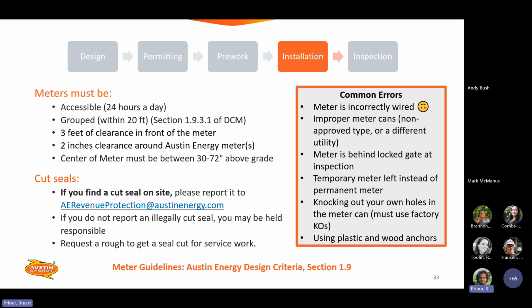Quick tip is also that it's going to be a 200 amp meter can with the bypass handle. This is for residential self-contained meters, but if it's not the right one... Also, if the meter is behind a locked gate at the time of inspection, we do need access to all that equipment. If you've left a temporary meter instead of a permanent meter inside of a meter can to operate, that is not acceptable. So just be sure that your system is not energized when we show up for inspection.